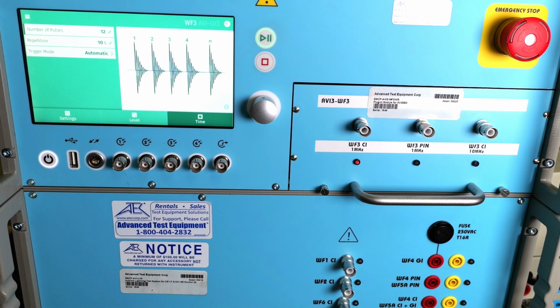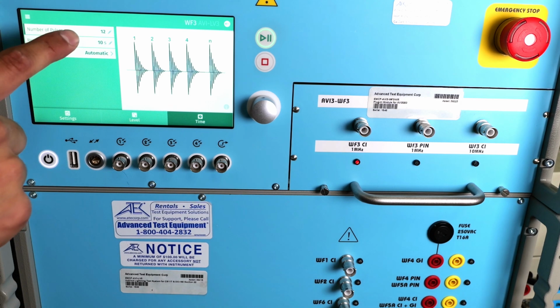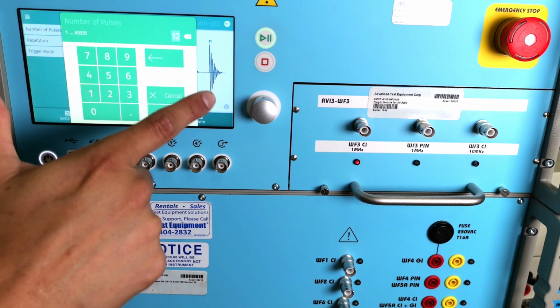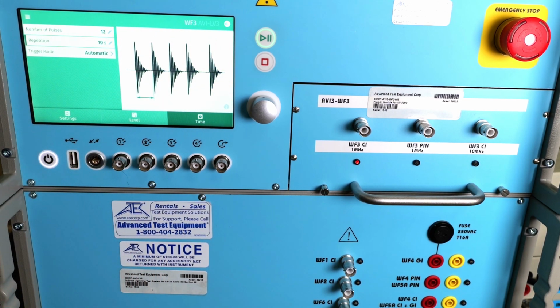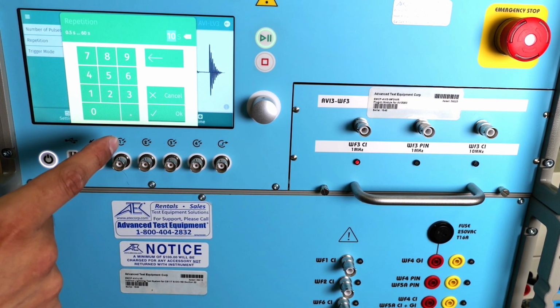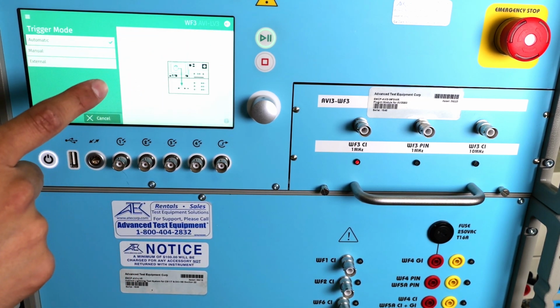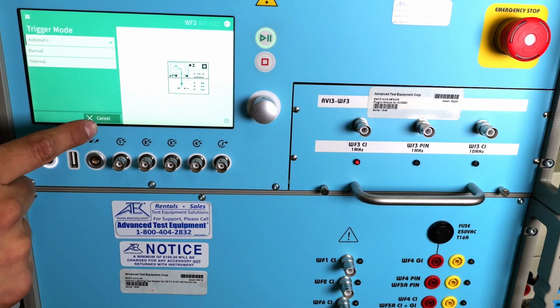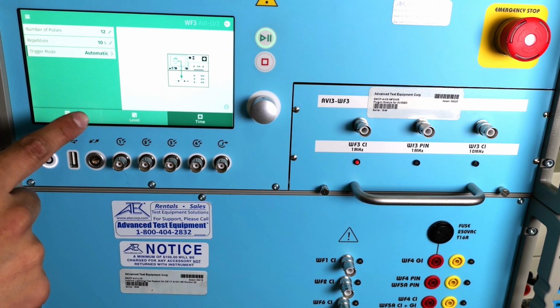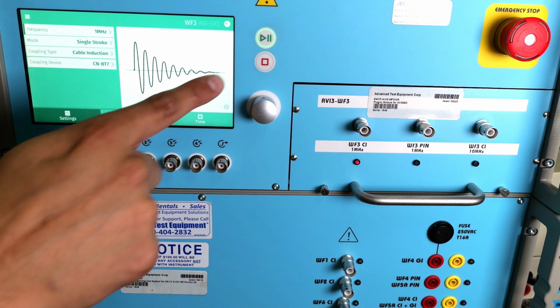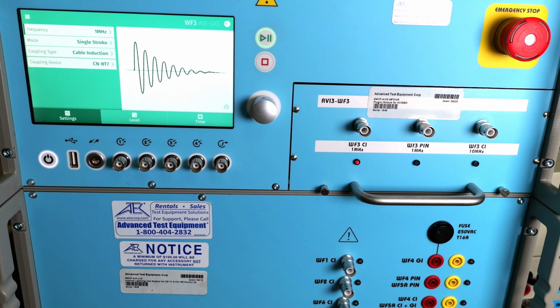Next, I'm going to do the timing menu, and I'm going to select the number of impulses I'm going to have the generator output, from 1 to a very large number. Then the repetition, from half a second to 60 seconds, and whether the trigger is manual, external, or automatic. Now once I have all this set, this green button is going to output the waveform. But first I'm going to connect an SHV cable to my BT7 probe. So I'm going to grab my cable now.